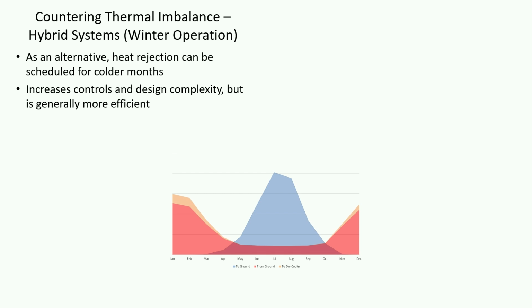It requires a fairly sophisticated BMS system, so you need to track over the course of the year how many more BTUs are going into the ground than coming out. And then you will design your system to be controlled to run for enough hours and reject enough heat throughout the entire course of the year to make up that difference.